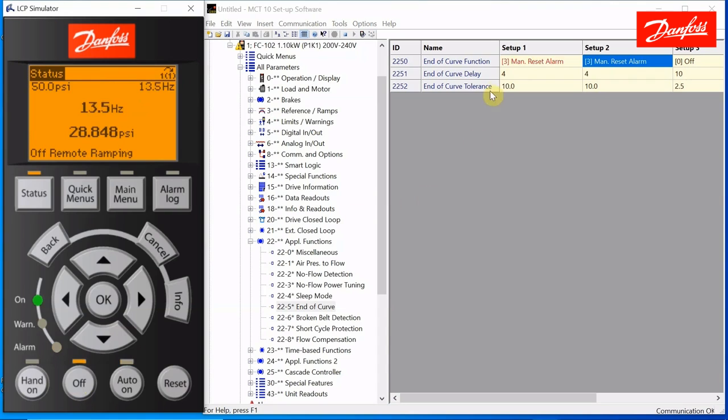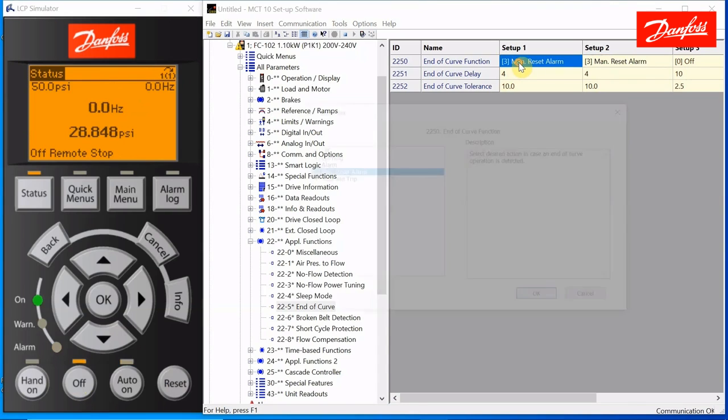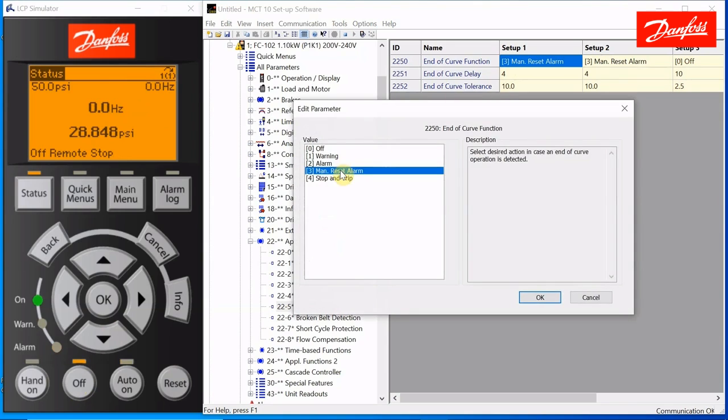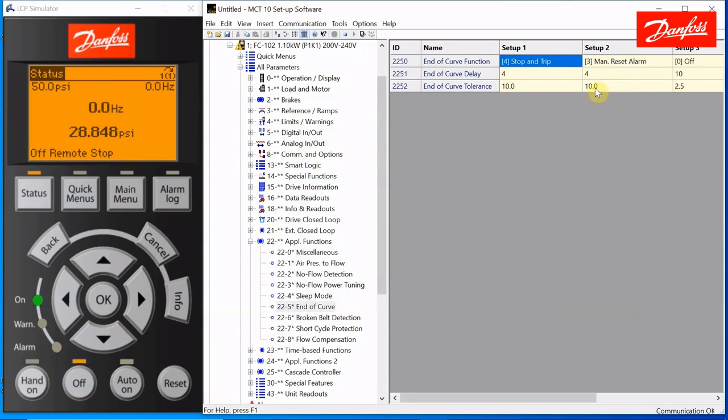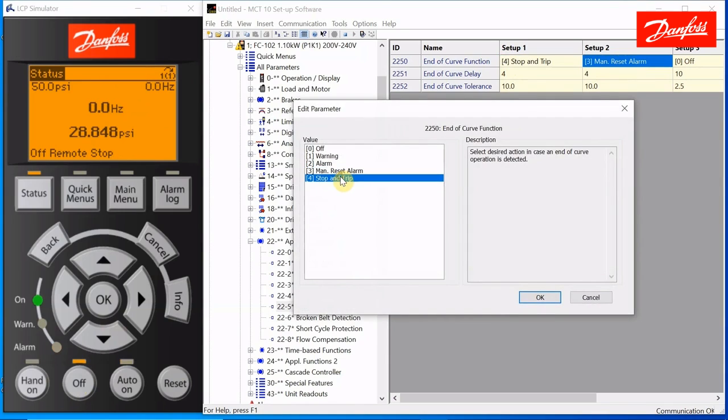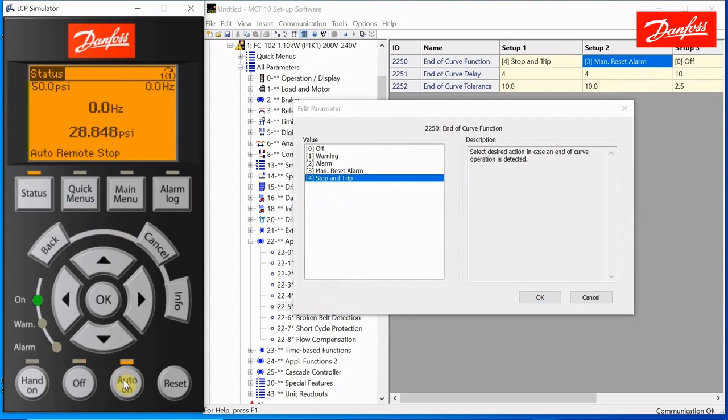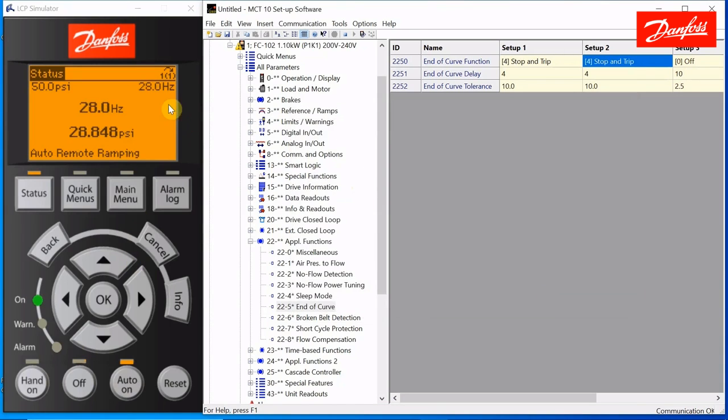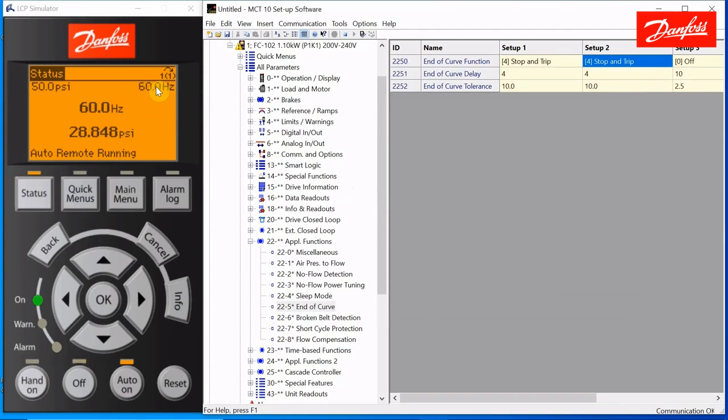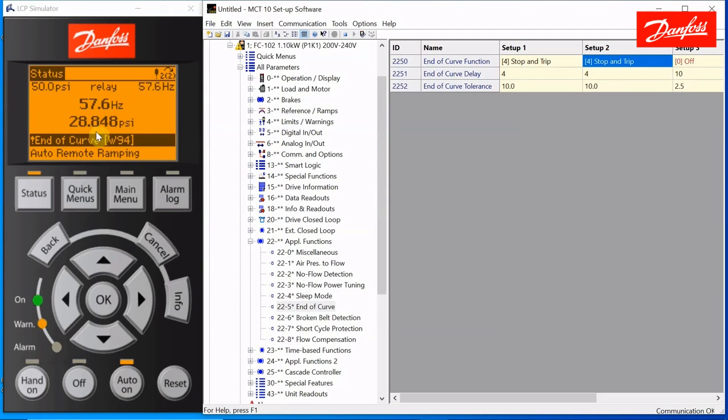Let's give it a stop, and let's look at our next choice here. You can choose to have the drive stop and trip. What's the difference between stop and trip and alarm? It still goes into an alarm state, but it gives a stop command, meaning that it's not going to instantly drop down to zero hertz. It's going to follow a ramp down time. Maybe you've got a check valve ramp designed in there, or an end ramp, or a post lube, or maybe you want this drive to not just drop to zero speed. So it's at full speed. The pressure is low. It trips, and it's following the ramp down time.